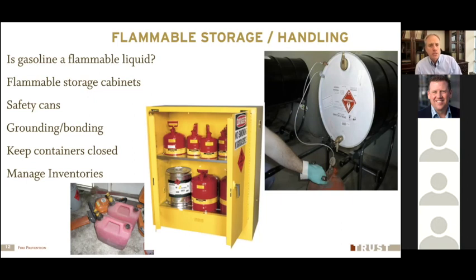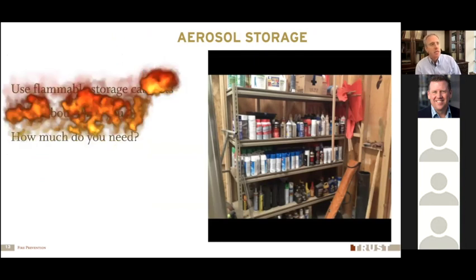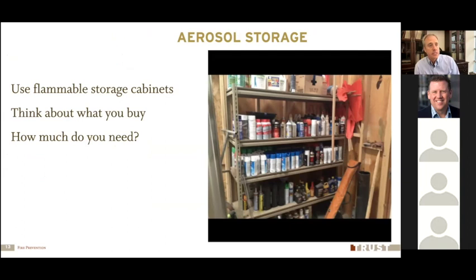Manage your inventories too. Sometimes we just see way too much of something stored in a facility. Flammable aerosols is something that we frequently see, just virtually hundreds of cans of flammable aerosols stored in a facility. And if we should have a fire in this facility, as those cans get hotter and hotter, eventually they explode. And when they explode, that flammable liquid inside of them sprays all over the place. And so not only do you have this explosion and flying aerosol cans, but you're also spewing that fuel around to make the fire even worse.